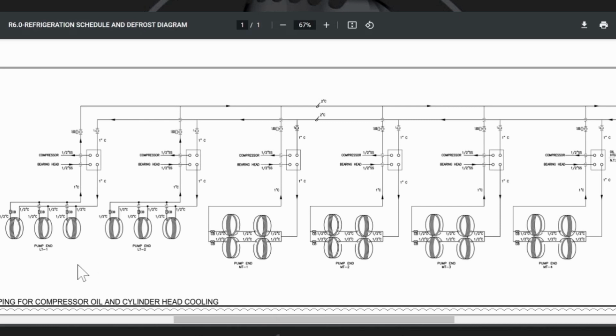All right. So what I see down here at CB, I don't know what CB is. Do you know what that is? That's a balance valve. Okay, so you actually have balance valves on here, because if anyone doesn't know, in industrial refrigeration you can use glycol water, or sometimes they'll even use liquid coming from the thermal siphon off of the condenser to basically chill the heads. Sometimes I've seen expansion valves also run on this. Right. There's a multitude of ways that you can do it, but this is the way that they decided to do it. So you actually have balancing valves on there.